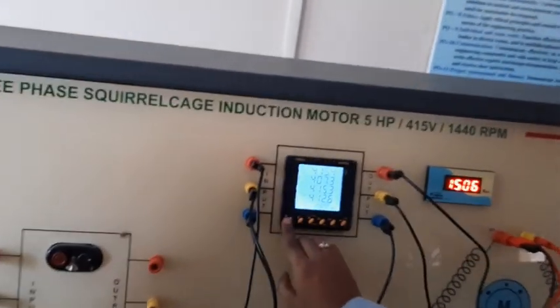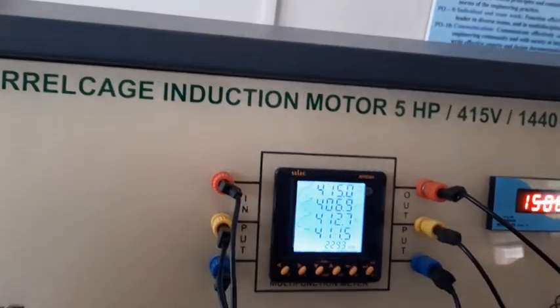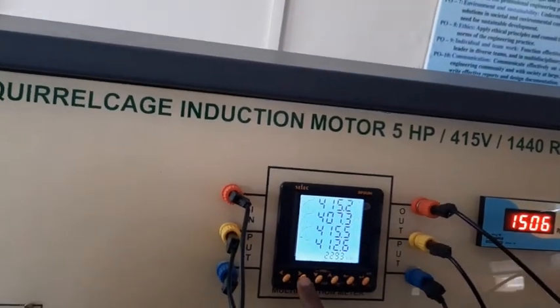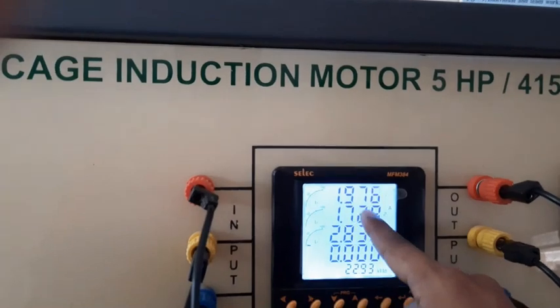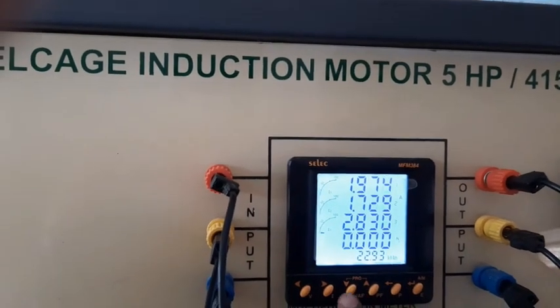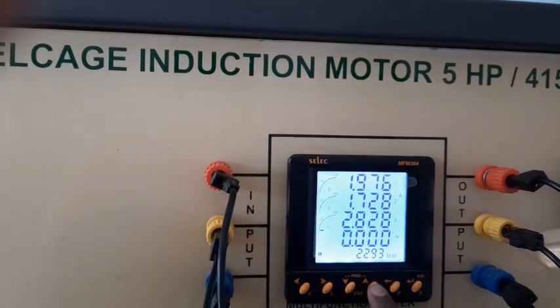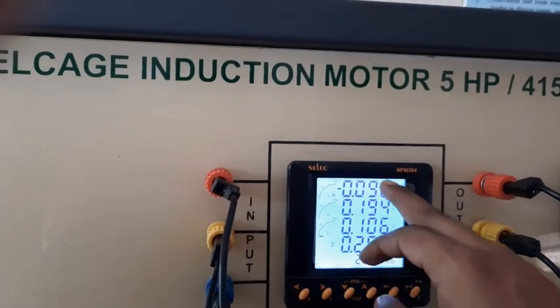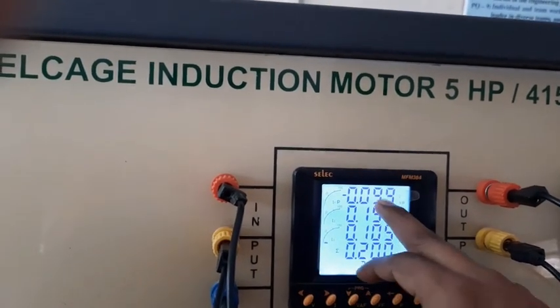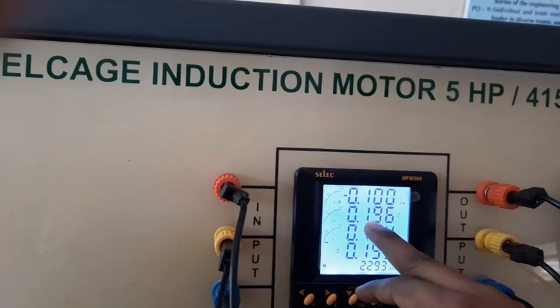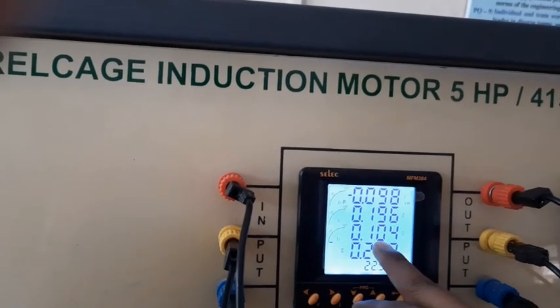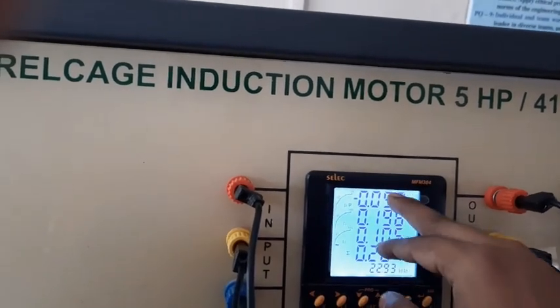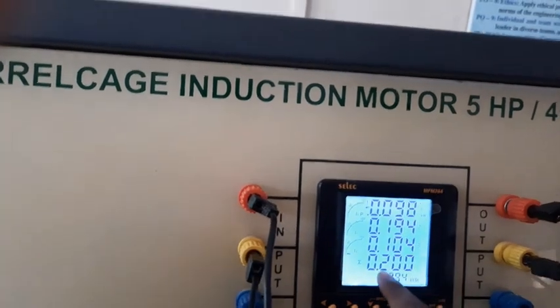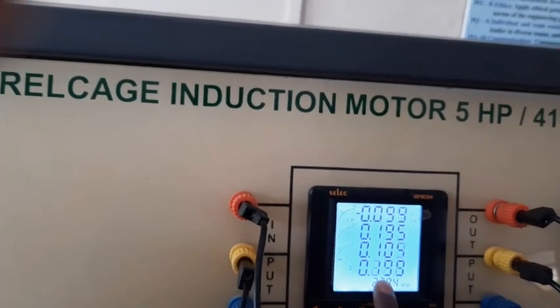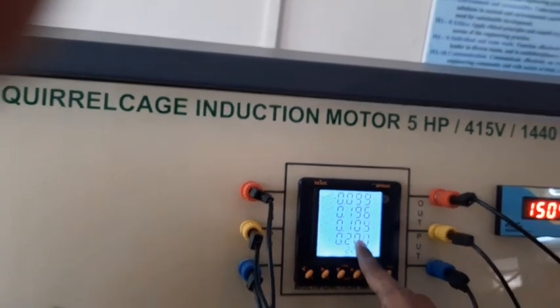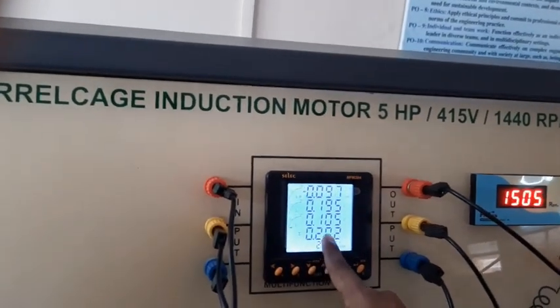Now we have to take the voltage reading as 415 volt and the current reading as 1.9 ampere. And for the power reading, you have to take the summation of the readings. Individual readings: R phase 99 watt, Y phase 196 watt, B phase 104 watt. So this is minus 99 watt. Therefore the total wattage is 200 watt. This is called W0, the no load power.